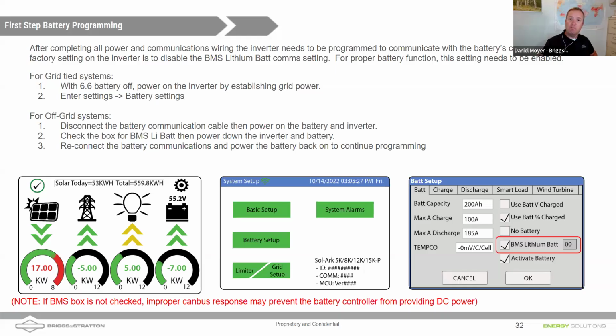That will enable the battery communications between the inverter and the battery. If you have an off-grid system, it's a little similar. If you're off-grid, you don't have grid to power on the inverter, so leave the communications unplugged, use the battery to turn on the inverter, do that checkpoint, and then you can turn everything off and reconnect the cables as well.